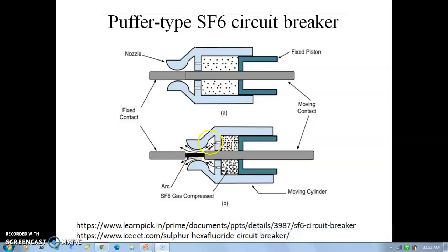When the arc is formed, nozzles open due to gas pressure and the compressed SF6 gas comes between the two contacts. It enters the arc position, combines with the electrons, and the SF6 gas cools the arc down. Arc is extinguished and current comes to zero.